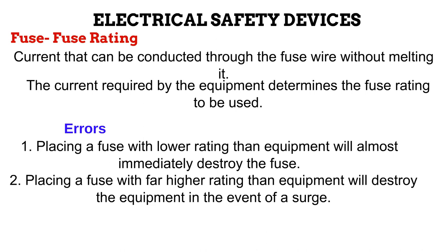If the error of using a fuse with far higher rating is made, the equipment will be destroyed if a surge occurs. For example, equipment needing 15 amperes protected by a 30-ampere fuse: under normal conditions, 15 amperes flows fine through the 30-ampere fuse. However, if an electrical problem causes excess current of, say, 25 amperes, this high current would not melt the 30-ampere fuse — it would reach the equipment and damage it.